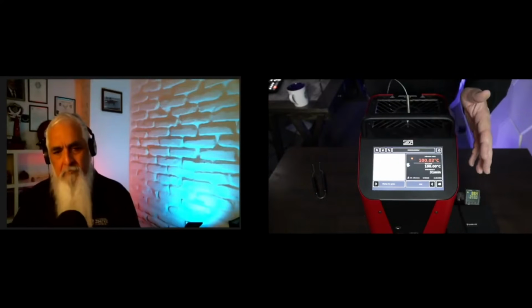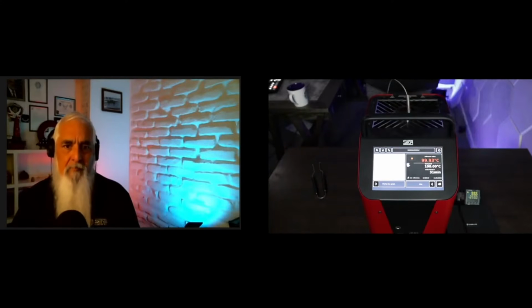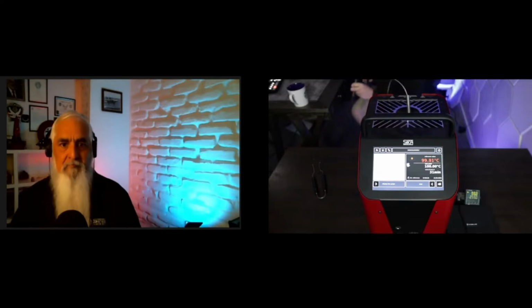One like this has a set amount of time that it's gonna sit at temperature before it shuts off, but that time starts after it has settled. Other ones, it might get up to temperature or get over the temperature, maybe 5 degrees, 2 degrees, and then it's going to settle back possibly down under and then bring it back up. So some of the characteristics you just need to be aware of, sometimes those temperature wells will not be perfect.